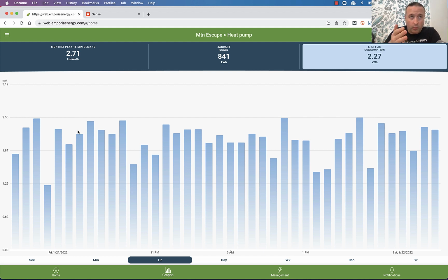Like I said, 1,000 watts running full tilt pulls a kilowatt hour per hour. A ton basically works out to be 1,000 watts. It's going to vary a little bit. There's various games that can happen within that. But ballpark, 1,000 watts is a ton. So if we're using 2 kilowatt hours an hour, or 2.5, it's basically getting to 2.5 tons. And that makes sense because it will pull as much as 2,500 watts, even though it's only supposed to pull 2,000 for 2 tons. So that is what I'm seeing in the operation of it.